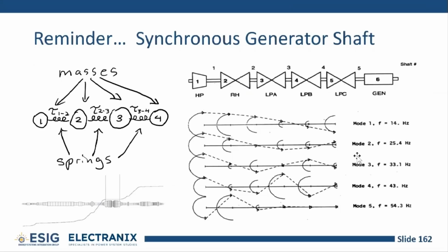Since that time, 50, 60 years later, we now have a long series of studies that we do every time you add a new synchronous generator near a series capacitor, or should be doing. Every time you put a new series capacitor in, there's a whole set of studies that need to be done, or should be done. Actually, they do need to be done, not always being done now, but this is old science.